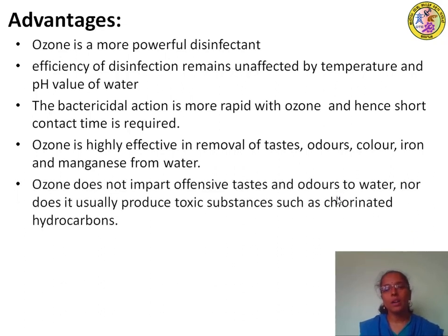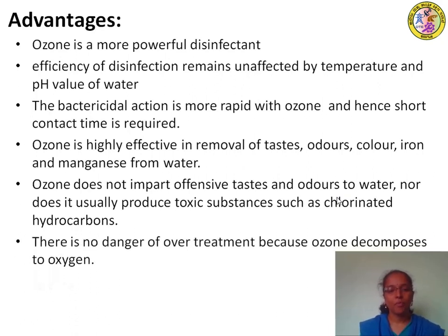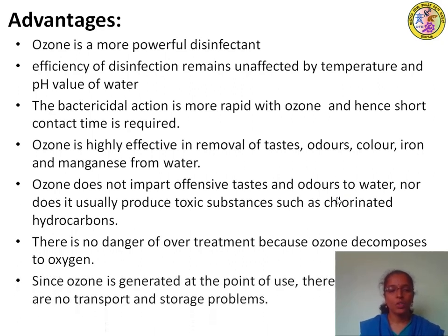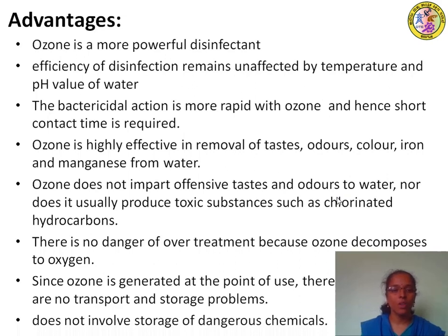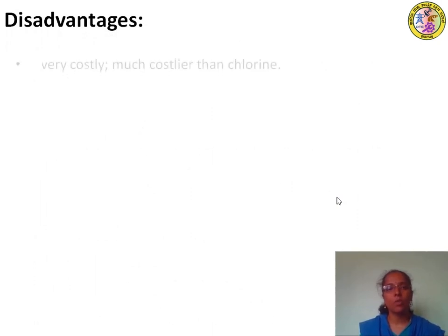It does not impart any offensive taste or odor to water, and it does not produce any toxic substances such as chlorinated hydrocarbons. There is no danger of over treatment because ozone decomposes into oxygen. Since ozone is generated at the point of use, there are no transport and storage problems. These are the advantages of using ozone as a disinfectant, and it also does not involve any storage of dangerous chemicals. Next, the disadvantages of treatment with ozone.